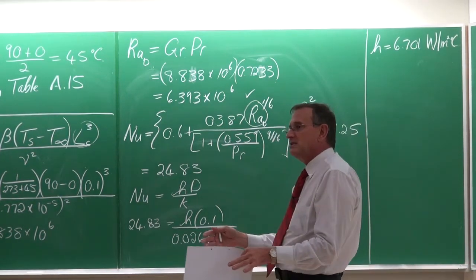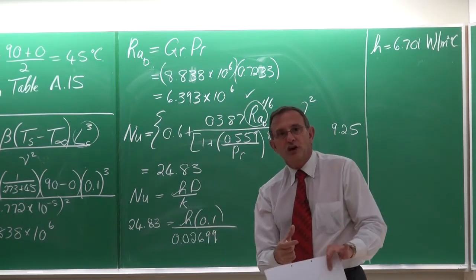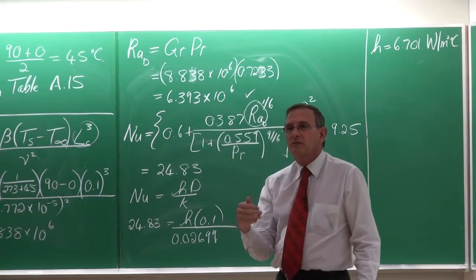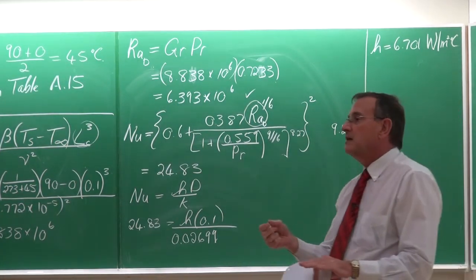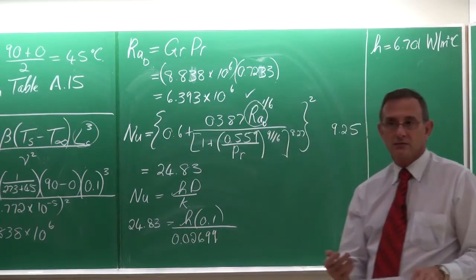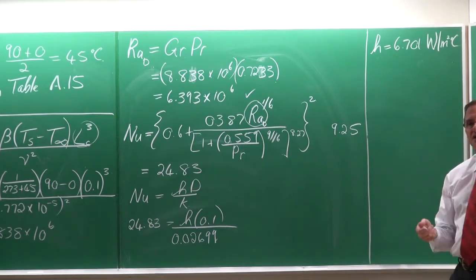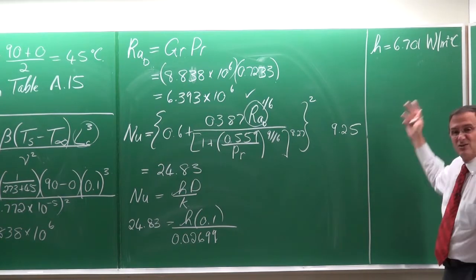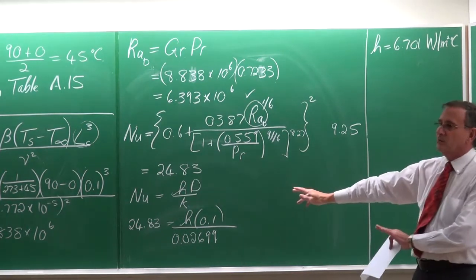If we've got single-phase forced convection — water, air, or something like that — heat transfer coefficients are normally on the order of thousands. If we've got condensation or boiling, then the heat transfer coefficients are on the order of tens of thousands. This is always something important to realize, so you know whether your answer is about right. If the answer was 6,701, you should know something is wrong.